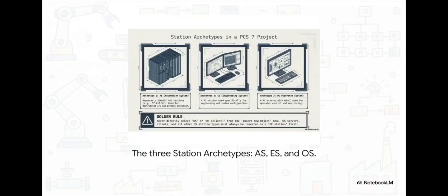Now listen up, because there is a massive pitfall here that traps so many engineers. Never, ever directly select OS from the Insert New Object menu. Every operator system must always be inserted as a PC station first. Bypassing this is a really common, costly mistake that will completely break your integration.